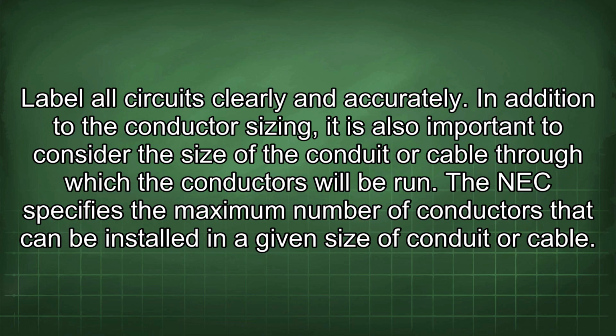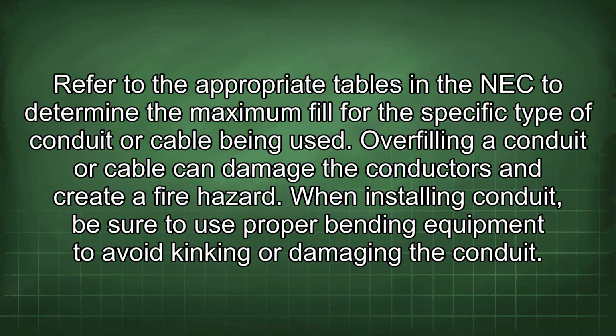In addition to the conductor sizing, it is also important to consider the size of the conduit or cable through which the conductors will be run. The NEC specifies the maximum number of conductors that can be installed in a given size of conduit or cable. Refer to the appropriate tables in the NEC to determine the maximum fill for the specific type of conduit or cable being used. Overfilling a conduit or cable can damage the conductors and create a fire hazard.